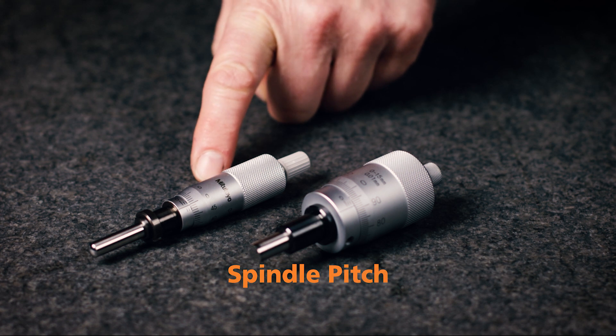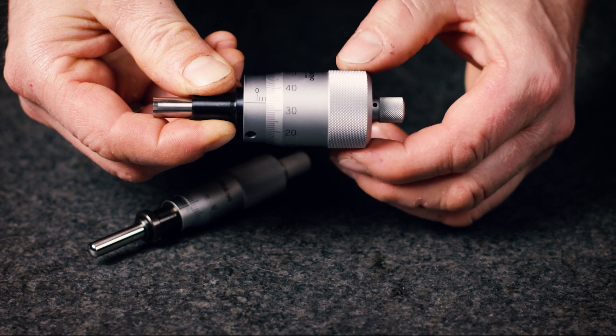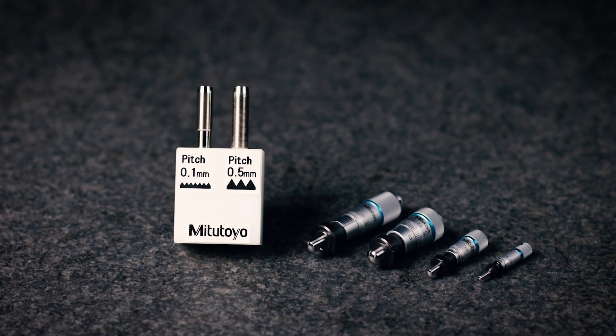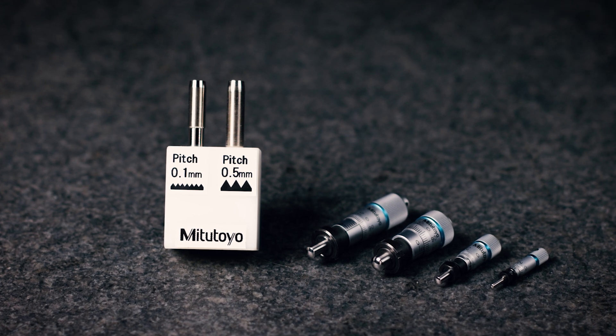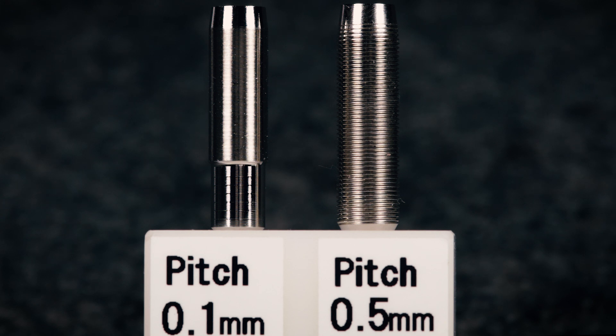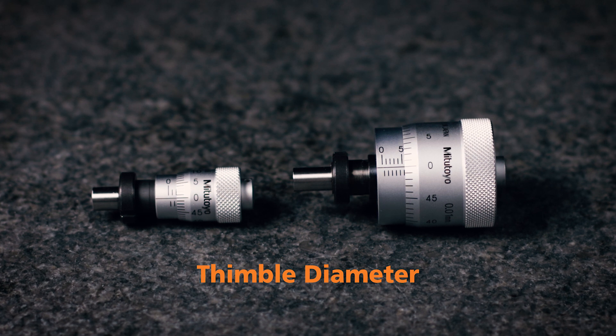The standard type head has a 0.5 mm pitch, but a 1 mm pitch type is quicker to set than a standard type and avoids the possibility of a 0.5 mm reading error. For ultra-fine feed or ultra-fine positioning applications, a 0.25 mm or 0.1 mm pitch type is the best to use. Mitutoyo is able to provide a micrometer head with a 0.1 mm pitch, something that is unique on the market.